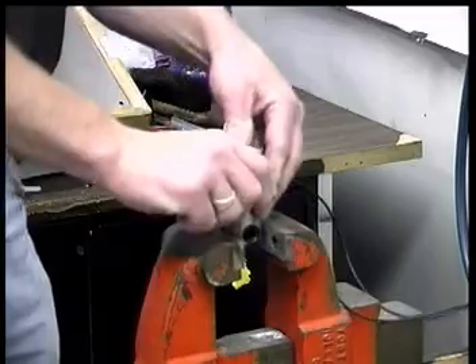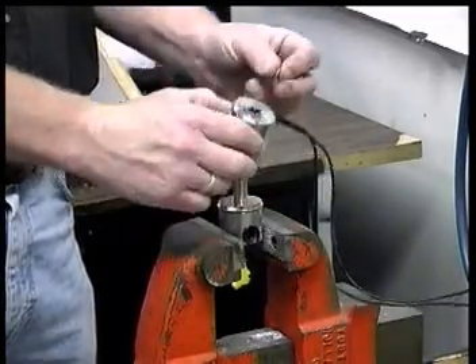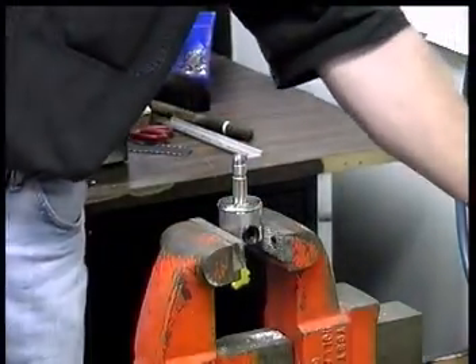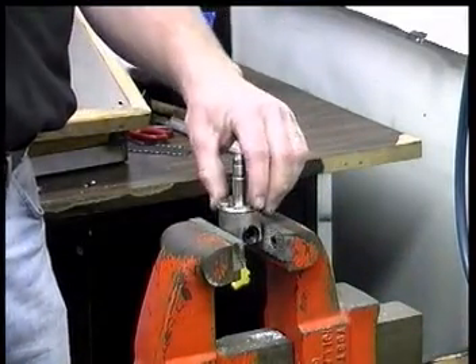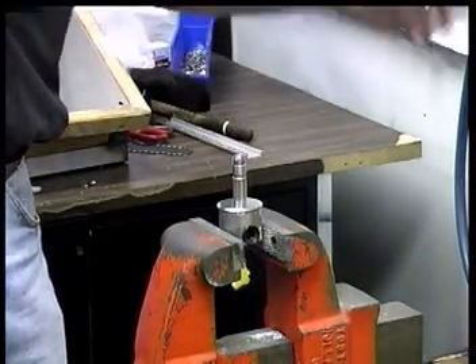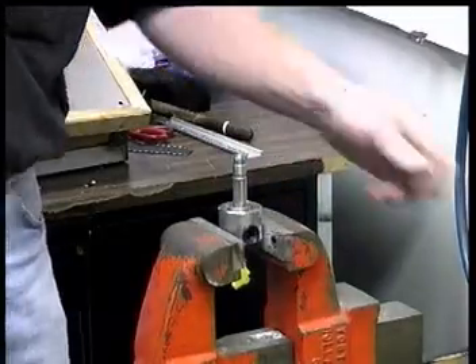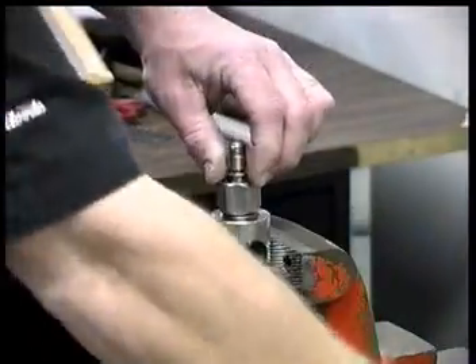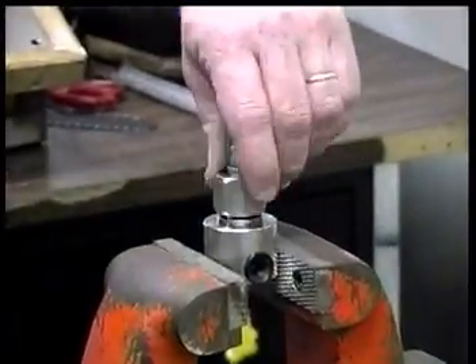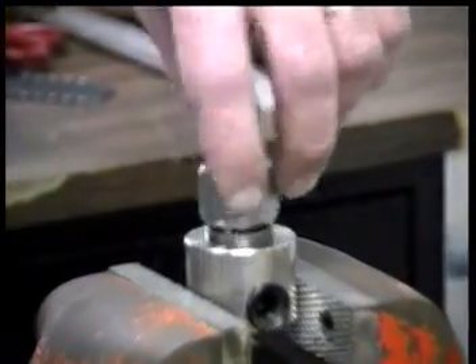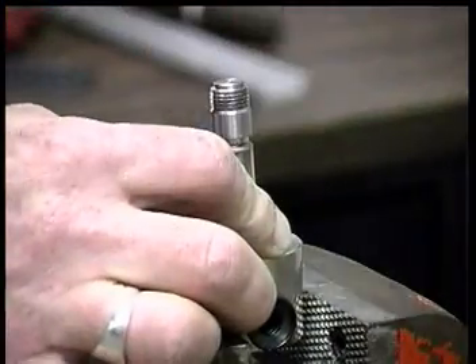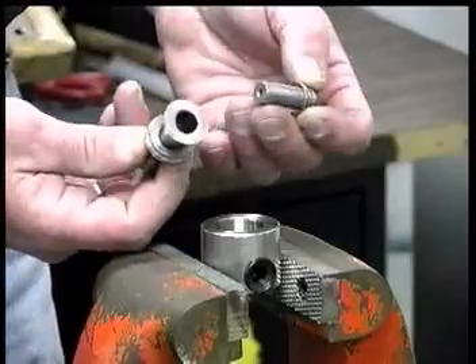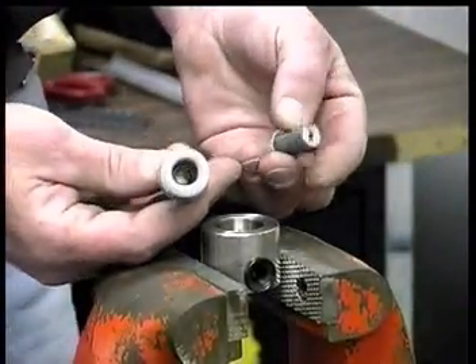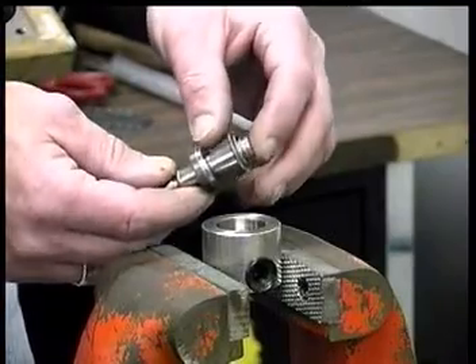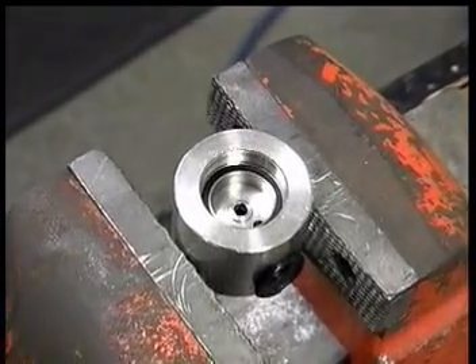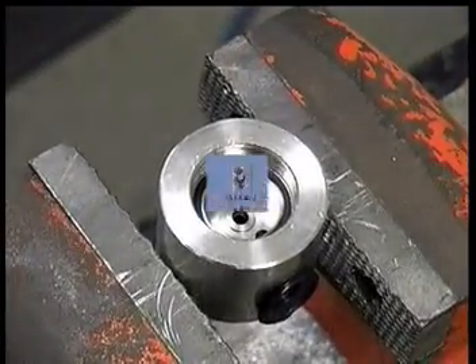The low-pressure solenoids are simple to maintain. Begin by removing the coil from the stem. Never remove the coil when there is power on it. Doing so will cause the coil to fail immediately. Once the coil is removed, remove the stem by turning it counterclockwise. The removal tool shown is available through our parts department. The stem contains loose components. Be careful when removing. Verify the plunger and spring move easily and there is no damage to the seat. Check for any blockage in the valve body. If none, reassemble the valve.